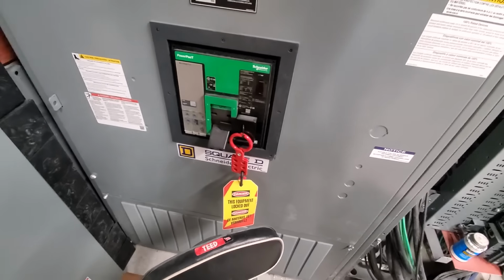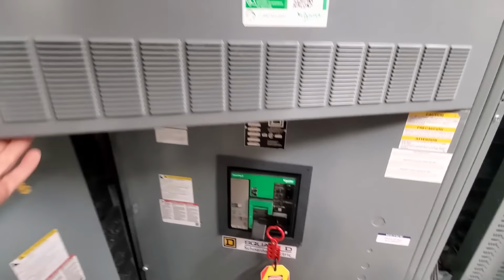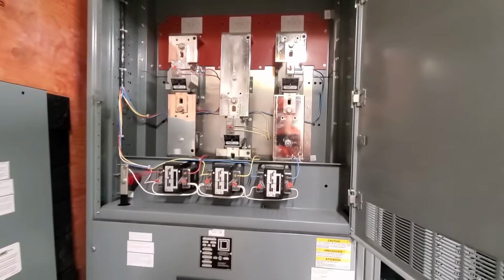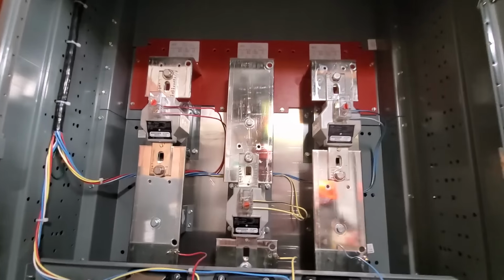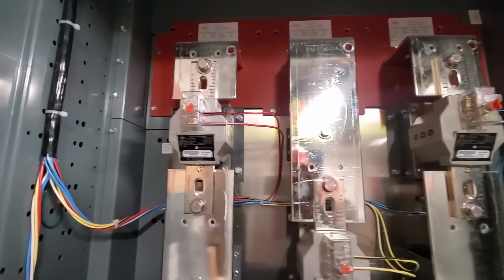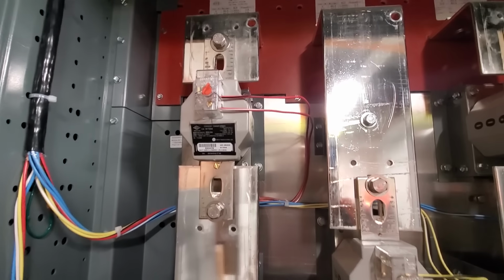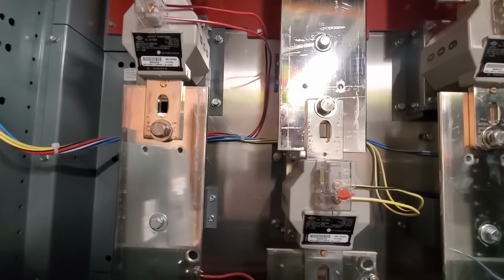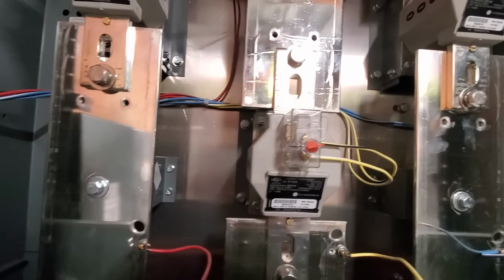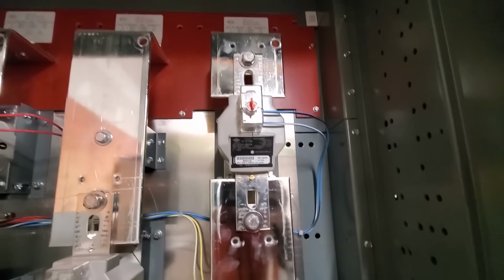Just above the main breaker, we have a cabinet that has the PTs and CTs enclosed. That's the current and potential transformers. It's a bar type. So those are conductors, those huge metal plates, and the power flows through those CTs and transforms that at a 120-to-1 ratio.